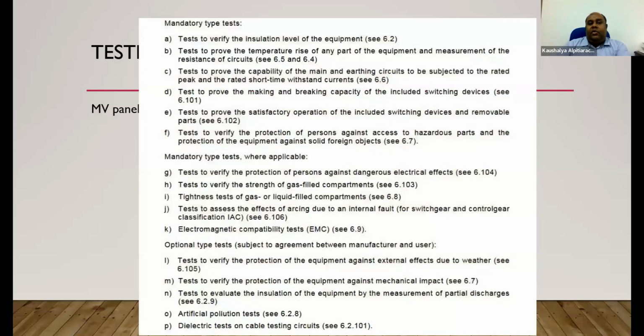MV panel testing. You refer to 62271-1. You have a series for mandatory type tests and other type tests, and optional type tests depending on the manufacturer and the purchaser. You can refer to 62271 part 6. The complete detail is there.